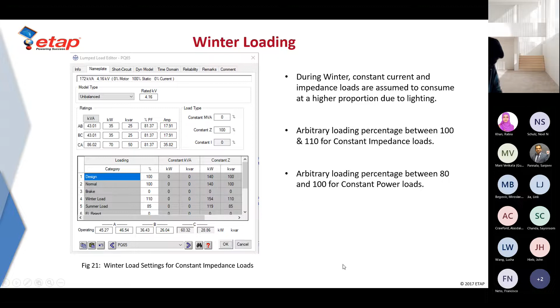When you combine everything and run the feeder summary, we have the results as shown. In summer there is a higher consumption compared to winter, but both of these numbers are lower than the design and rated, simply because the IEEE datasheet does not have any diversity factor associated with it, and everything runs at the rated, which we know in practice does not happen.